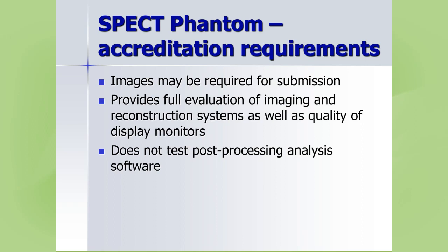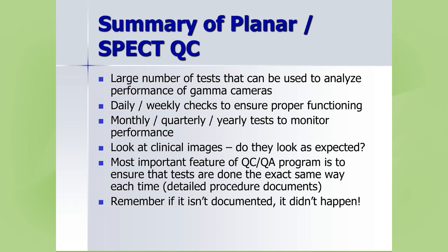In summary for NucMed/SPECT: there are many tests to analyze camera performance. Daily and weekly checks ensure proper functioning before patient use. Monthly, quarterly, and yearly tests monitor performance over time and catch issues before they impact clinical images. Technologists should always look at clinical images and raise a flag if something doesn't look right. The most important feature of any QC/QA program is consistency — doing tests the same way each time. If it isn't documented, it didn't happen.